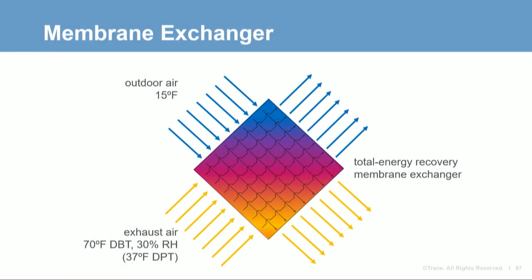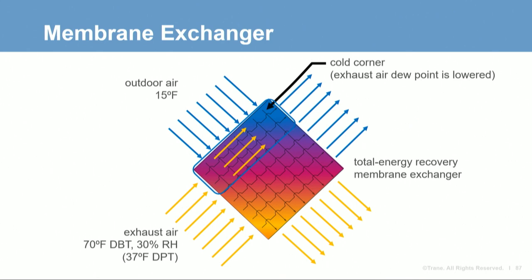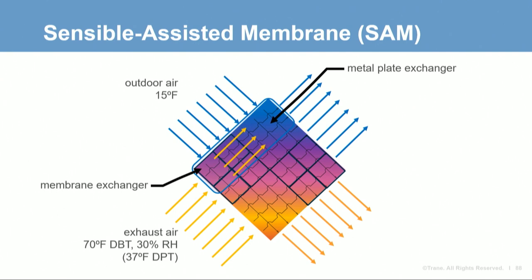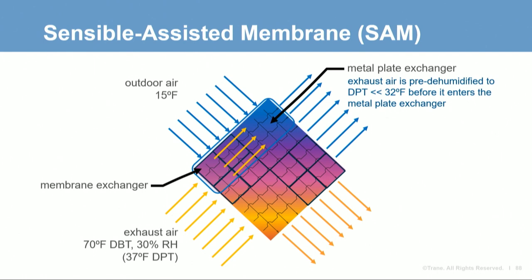Metal plate exchangers will require some means to reduce capacity to prevent ice formation. Some manufacturers add a frost avoidance damper to divert outdoor air away from the cold corner when ice may occur. A membrane exchanger is different: as the exhaust air is cooled while passing through the membrane, water vapor is also being removed and transferred to the outdoor airstream, reducing the dew point of the exhaust air and removing the risk of liquid condensate turning to ice.